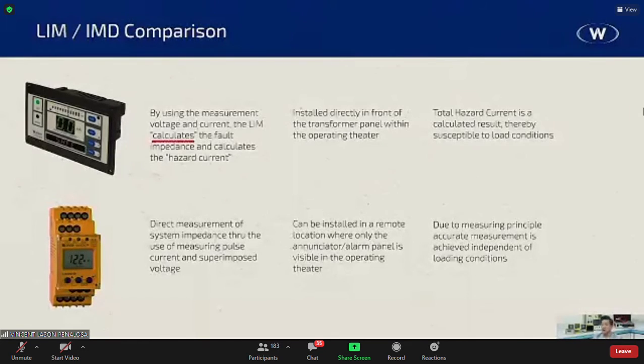Now, let's go to the IEC insulation monitoring device. As we mentioned a while ago, in the measuring principle, it's basically a direct measurement of system impedance through the use of measuring pulse currents and superimposed voltages. It can be installed in a remote location where only the annunciator alarm panel is visible in the operating theater. Let's say the operating theater is on the third floor and you have an electrical room there. That's where the isolation transformers can be, as well as the insulation monitoring device. And all that's gonna show up in the operating theater is the annunciator, right? So it's nice and clean. You have your alarms, and you're not going to have to worry about leakage capacitance.